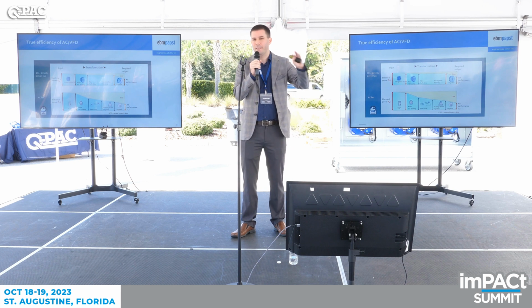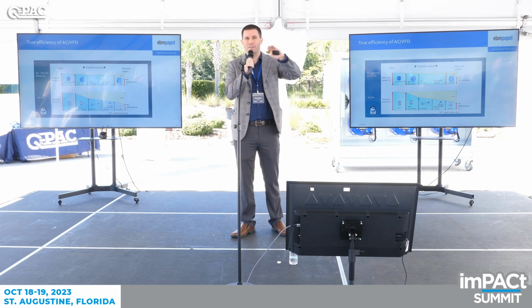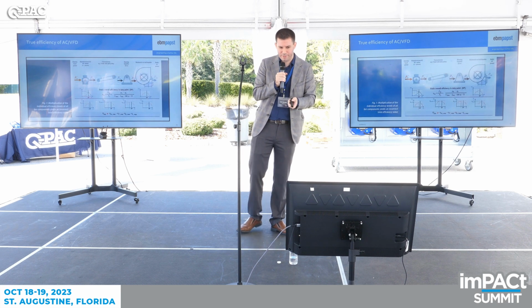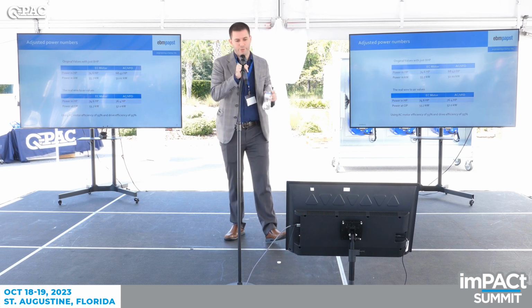Say that you take a motor that's 93% efficient and a drive that's 95% efficient. That's their peak efficiencies. So they're not all going to line up on the same exact spot. Unfortunately, that's a little tougher to figure out exactly how to compare those two. But the bottom line in this case was we just took a 95% efficient motor, 93% efficient drive, gave the drive and motor all the benefit of the doubt, and it still turned out the EC motor was more efficient when you factored it in. So that's just something you've got to keep in mind when looking at brake horsepower. It does not include motor and drive.